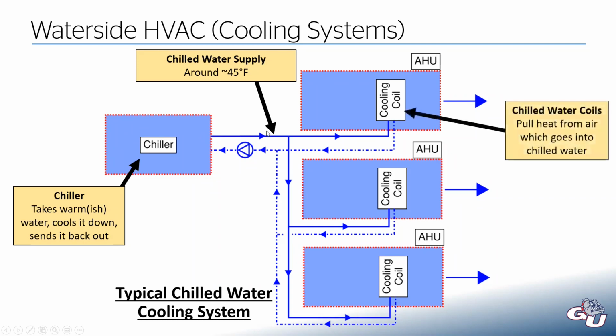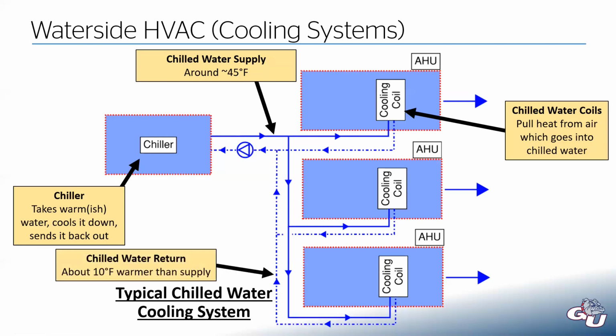This gets pumped out to a number of chilled water coils out in our air handling units. We run the chilled water through the coil, which pulls heat from the airstream that's going over the coil. So we end up with cooler air on the outlet of this air handling unit. And then the water is going to leave the coil a little bit warmer because it's absorbed heat from the airstream. All of the chilled water returns from all of our equipment out in the building is going to come back now into our chiller. And our return is going to be about 10 degrees warmer than whatever our supply is. So if we're sending it out around 45 degrees, the return will come back at around 55.